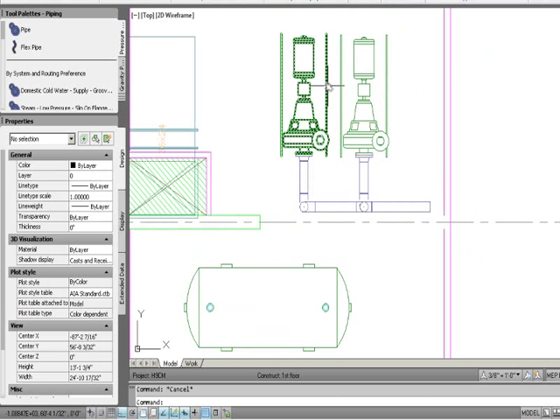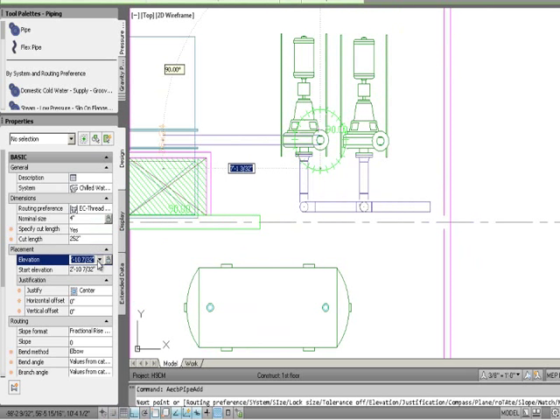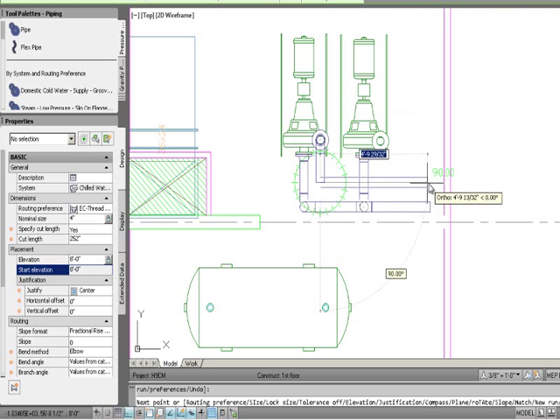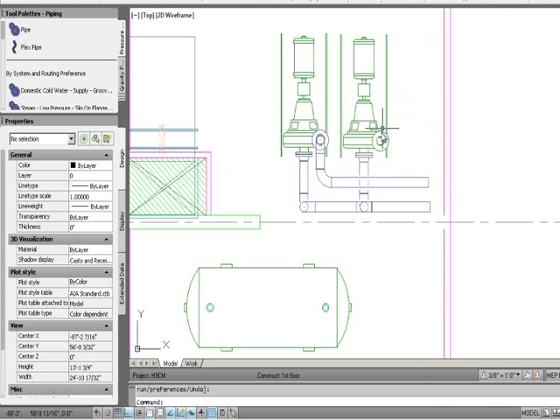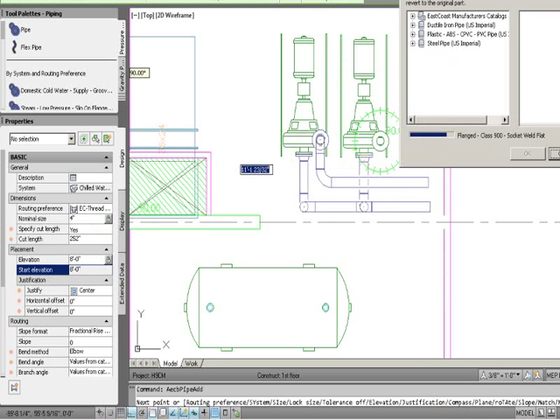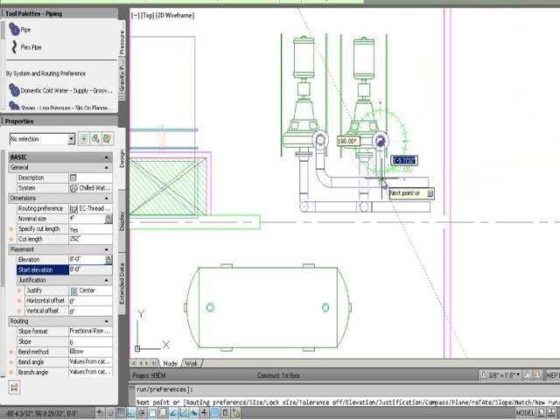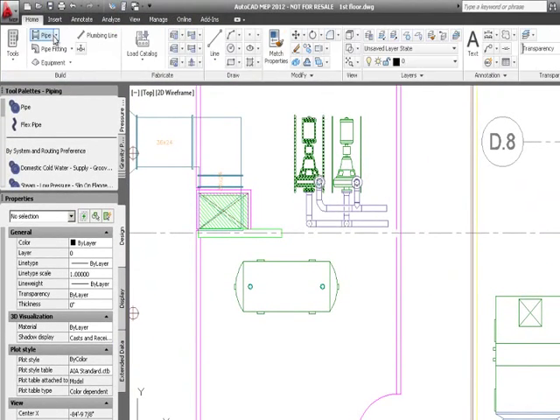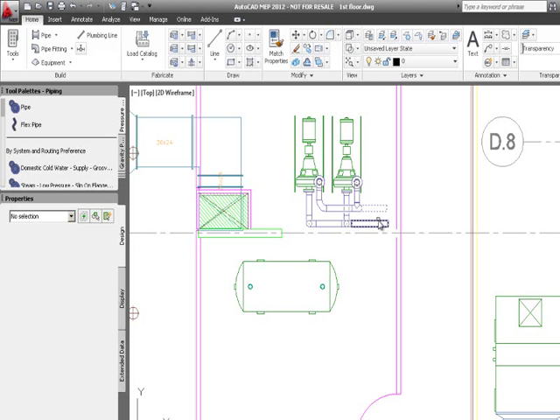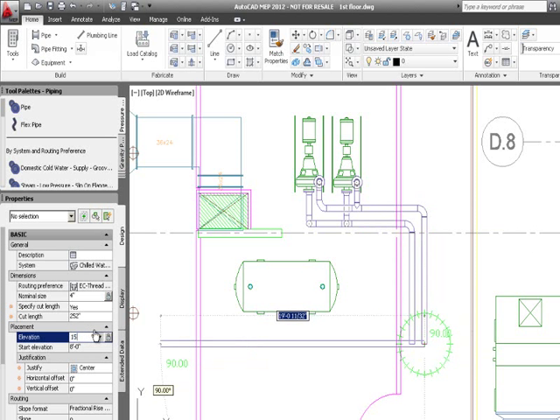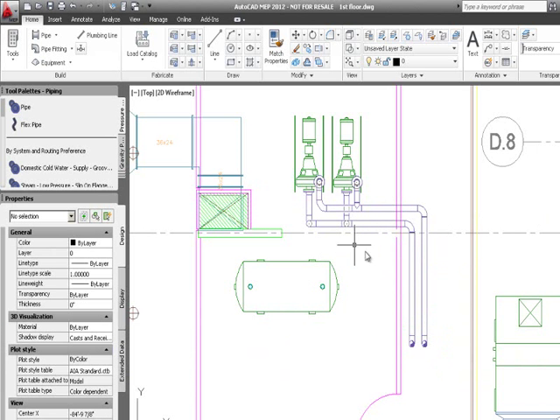It prompts me for the flange type again and I use my weld neck flange. I bring that run over and stop it at a location. I do the same off another pump, grab the grip, type in eight-foot elevation, pick the flange, and tie into another pipe. To continue these two runs together, I go to the parallel pipe routing preference on the Home tab, running both pipes simultaneously while maintaining their spacing — drawing them up to 15-foot elevation using parallel pipe routing.